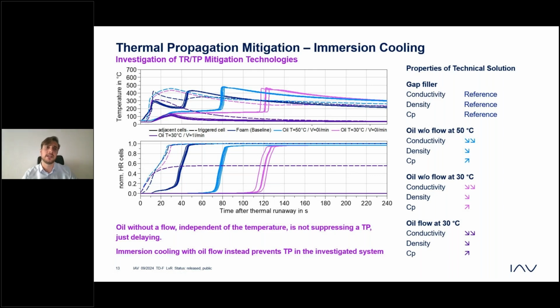But what we see here is that the adjacent cells are going into thermal runaway almost simultaneously. So we don't have this delayed propagation where one neighboring cell sees the runaway first, then another cell. If the oil is a bit cooler, we see that the delay is even stronger. Here we went from 50 degrees centigrade to 30 degrees centigrade, where we have a delay of this thermal propagation. And then in another case, these purple curves over here, if we add even a velocity to this oil, then in our case, we didn't see any propagation. So immersion cooling could be another procedure to avoid thermal propagation.